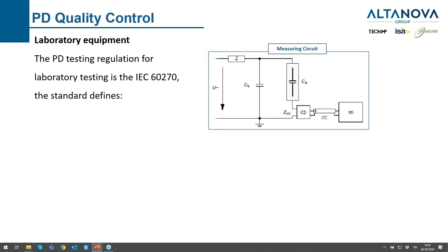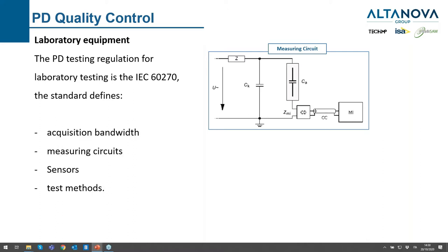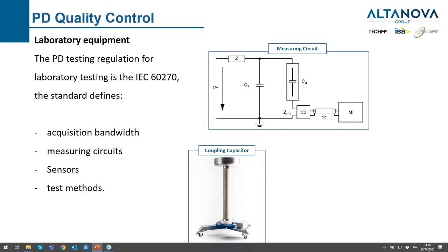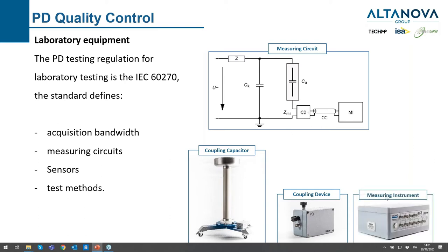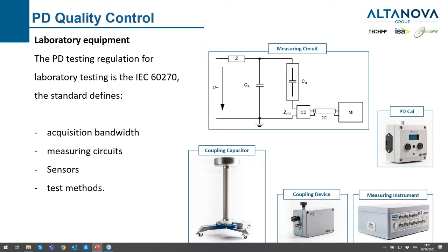When speaking about quality control in laboratories, we also need to follow all the single steps of the IEC 60270 and related IEC standards, which define the acquisition bandwidth, the measuring circuit, the sensor, and the test method. We will need a coupling capacitor (Ck), a coupling device (CD), and a measuring instrument. With this full set, including the PD base 2 and the PD calibrator, we can perform all the standard IEC 60270 tests.